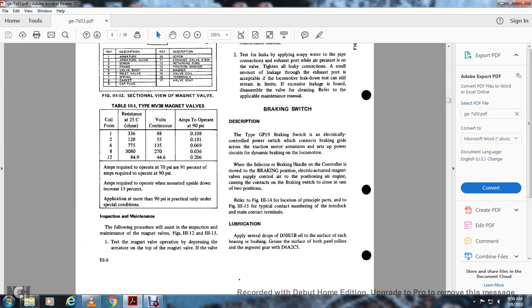Amps required to operate at 70 psi are 91% of the amps required to operate at 90 psi. Amps required to operate with the valve mounted upside down increase 15%. Application at more than 90 psi is practical only under special conditions.